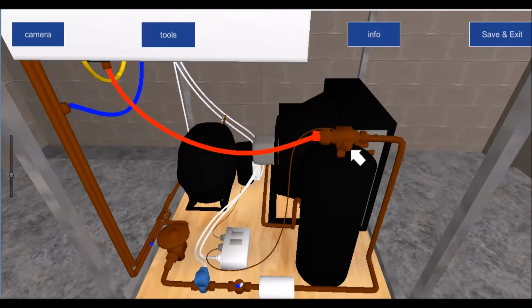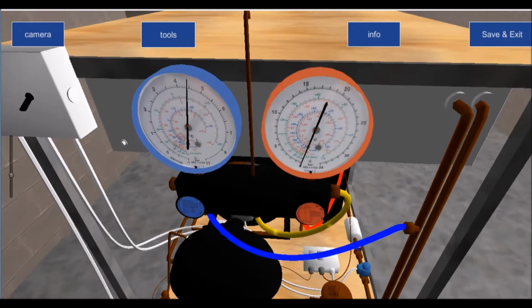So basically the terminology that we talk about is you have the valve in the fully backseat position. So this valve at the moment is in the fully backseat position. Then the valve can be cracked, and once you crack it, that means refrigerant can now enter into the red hose line, into the service line here, and we will get our pressure reading here on our gauge.